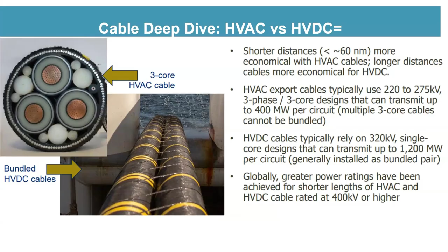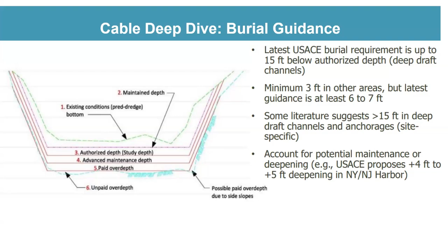So for burying the cables, just to give you a sense, you have to achieve federal permits from the U.S. Army Corps as you build these wind farms. The U.S. Army Corps currently recommends a burial depth up to 15 feet below the ocean floor. There are areas where they can have a minimum of 3 feet. And then typically 6 to 7 feet can be authorized too. But I think their preferred depth is deeper, just to avoid any interference on the seafloor bottom.